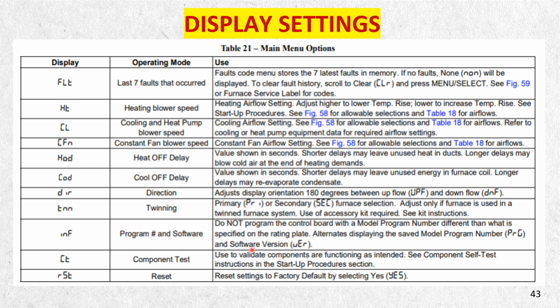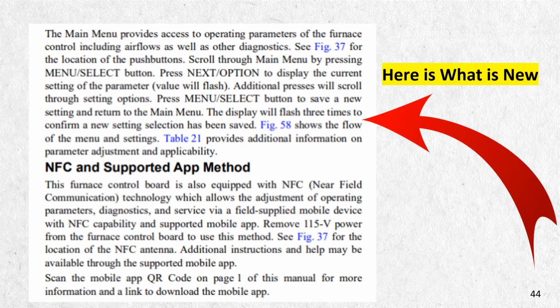If you have to change out your control board, do not do it unless you have this information, because that has to go back exactly the same, or your furnace will not run. And then you have a component test, and you can also reset it and go back to the factory default settings, in case there's a service tech that's no longer with the company, or a different company's service tech has gone in and changed speeds. You can hit reset and it goes back to the default factory settings, and then you can adjust it from there.